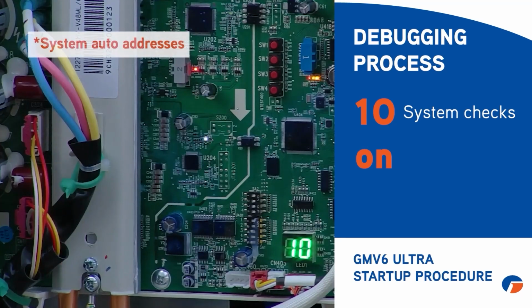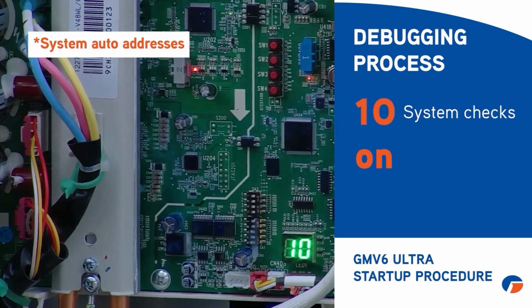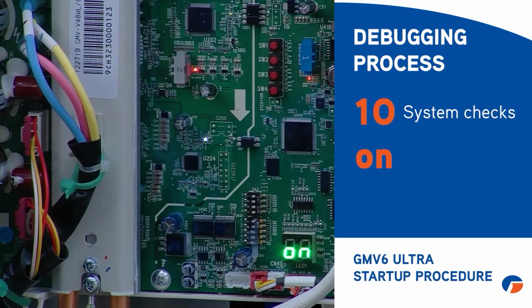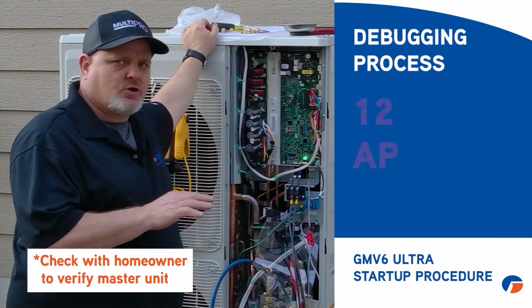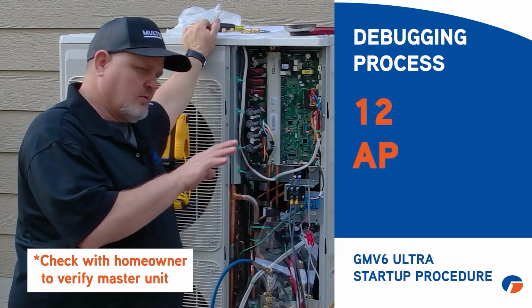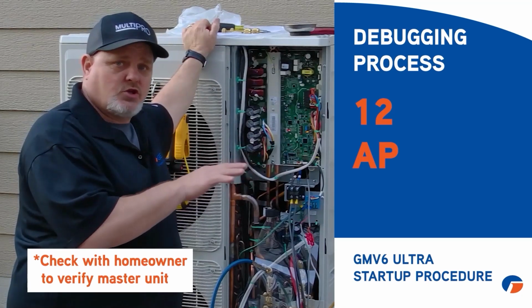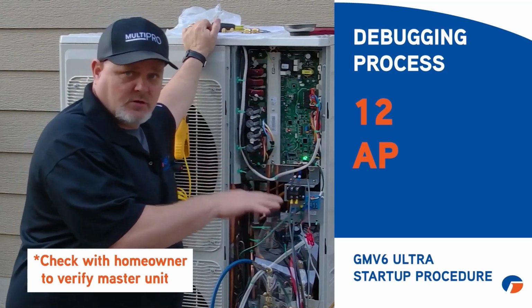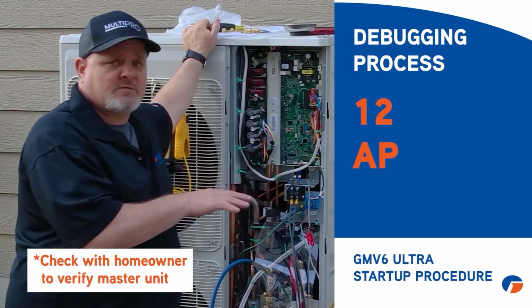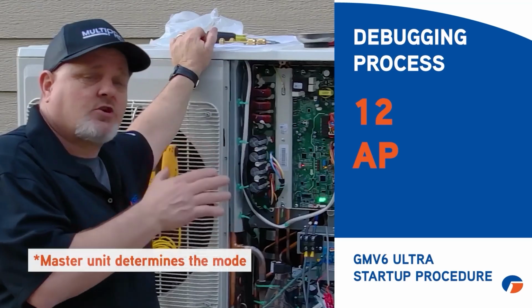Now, the other thing it does is auto address, same as the GMV5. So that's something to be mindful of. Once you commission the unit and they've addressed themselves, check with the homeowner and make sure that whatever unit was designated the master is the unit you want to be the master. It's going to pick one of those indoor units as master. So master determines mode.